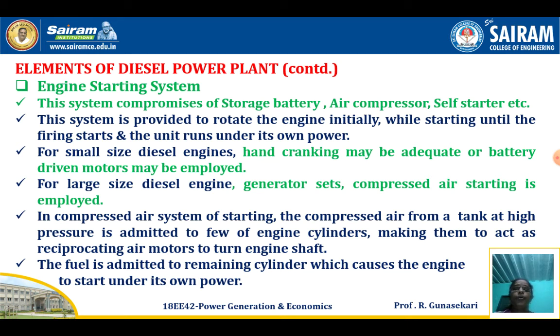Then engine starting system. This system comprises storage battery, air compressor, self-starter, etc. This system is provided to rotate the engine initially while starting until the firing starts and the unit runs under its own power. For small size diesel engines, hand cranking may be adequate or battery driven motors may be employed. For large size diesel engine generator sets, compressed air starting is employed.